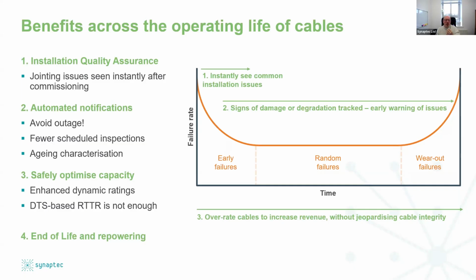So there's an installation quality assurance benefit of having green light available the moment you energize that circuit, because it's like a quality control. You're making sure it was installed properly and that what actually happens under load is what you expected. Having said that, there are obviously those automated notifications to avoid outage, and that could happen at any time through the life of an event. There are just random events where this happens. 10 years down the line, suddenly there could be a failure and everyone is surprised. But we don't ever talk about selling this technology and delivering it to customers on the basis that it'll fix or avoid these future failures alone, because failures in the future are unlikely and a long way away in the future.